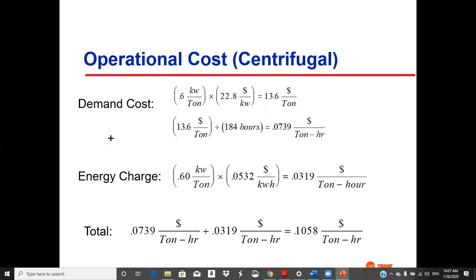Okay, so now we're going to look at the operating cost on the centrifugal, which we're comparing it to. This is 0.6 kW per ton. That's what it takes to run the chiller. And this is the demand charge, $22.80 per kW, so that's $13.60 per ton. Then this is the number of hours in the cooling season. They want to spread this out over the cooling season, over which we would be using energy at this rate while it was on peak and expensive. So a little bit of hand waving there. But anyway, the levelized cost of demand comes out about 7.39 cents per ton hour.